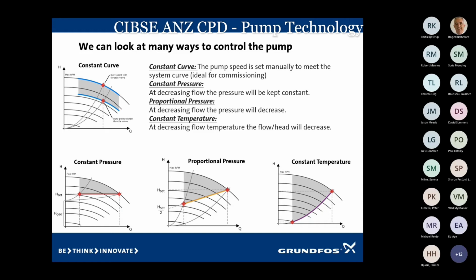Constant pressure, which is the one below. We use a lot of constant pressure in water boosting. Constant pressure also in heating and chilled water where the systems are not too large, but there's not a lot of pipe work. If the pipe work runs along, then we can use proportional pressure.